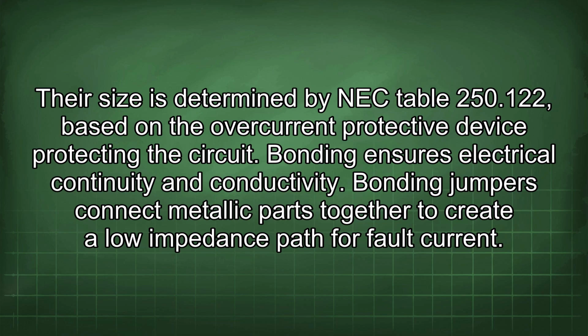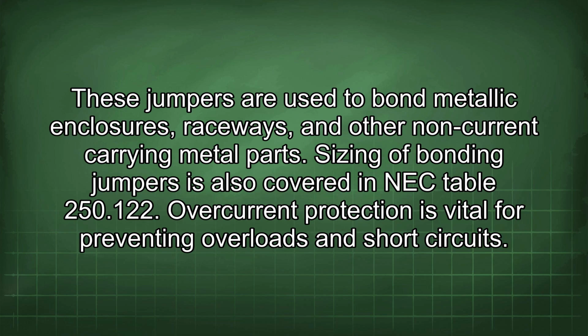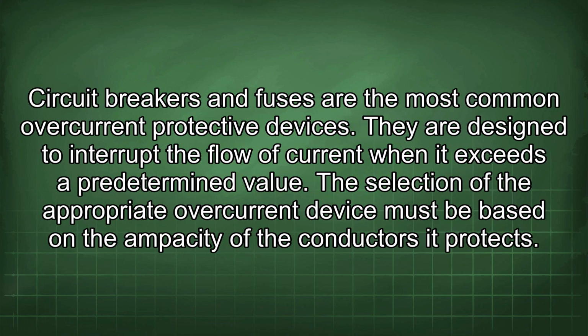Bonding ensures electrical continuity and conductivity. Bonding jumpers connect metallic parts together to create a low impedance path for fault current. These jumpers are used to bond metallic enclosures, raceways, and other non-current carrying metal parts. Sizing of bonding jumpers is also covered in NEC Table 250.122. Overcurrent protection is vital for preventing overloads and short circuits. Circuit breakers and fuses are the most common overcurrent protective devices. They are designed to interrupt the flow of current when it exceeds a predetermined value.